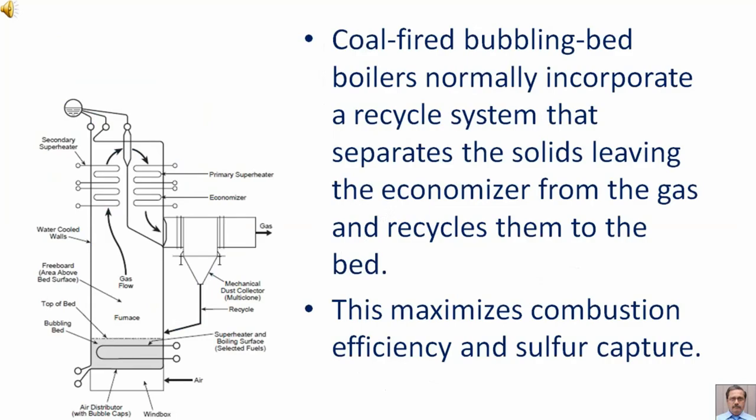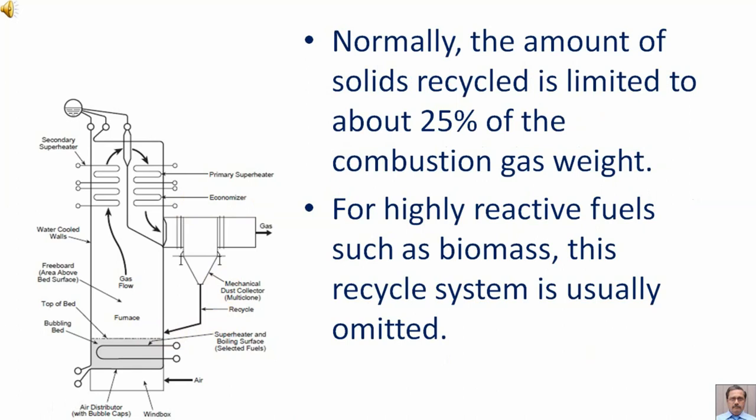Coal fired bubbling bed boilers normally incorporate a recycle system that separates the solids leaving the economizer from the gas and recycles them to the bed. This maximizes combustion efficiency and sulfur capture. Normally the amount of solids recycled is limited to about 25% of the combustion gas weight. For highly reactive fuels such as biomass this recycle system is usually omitted.